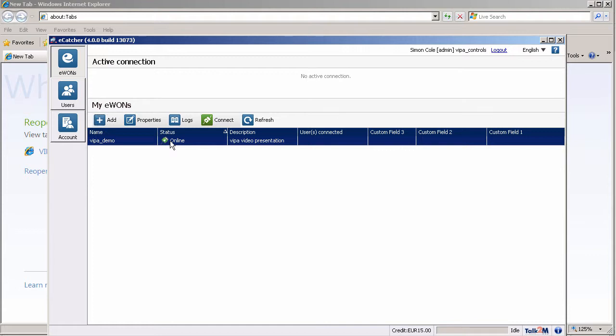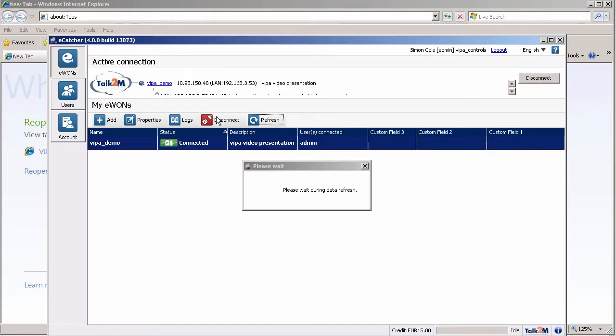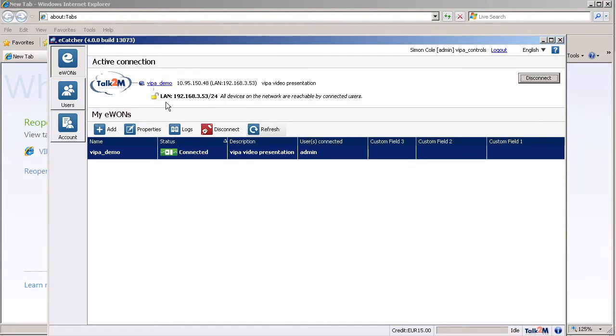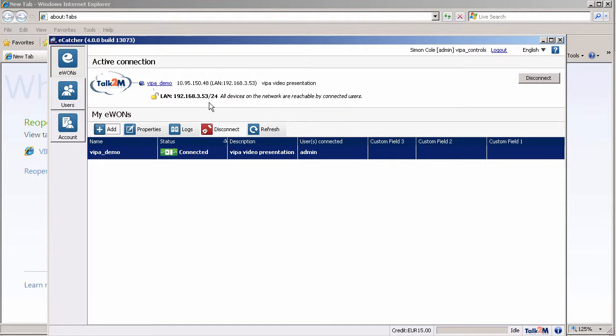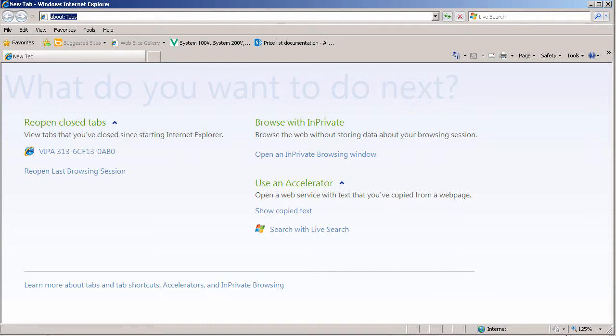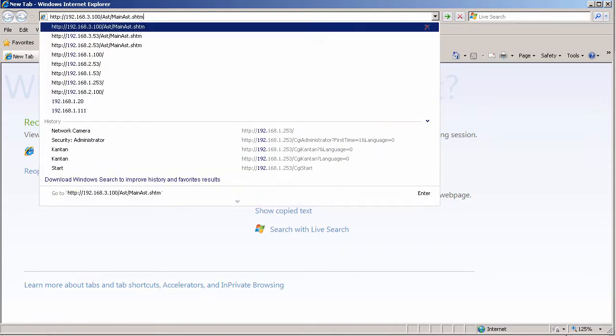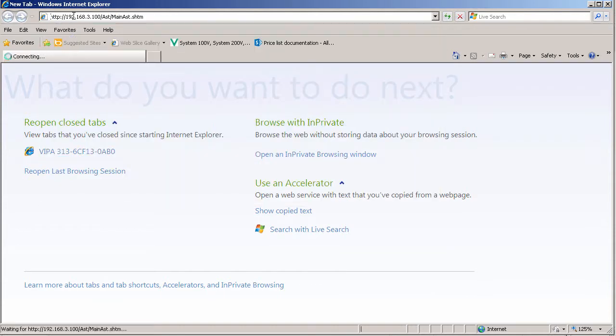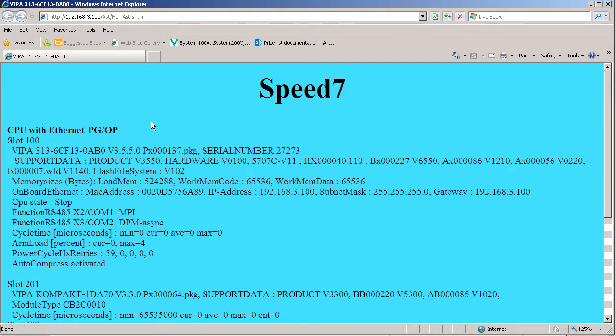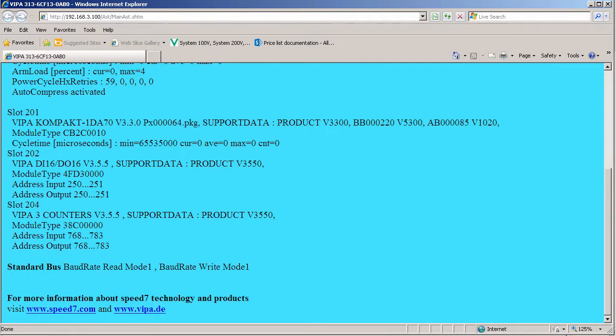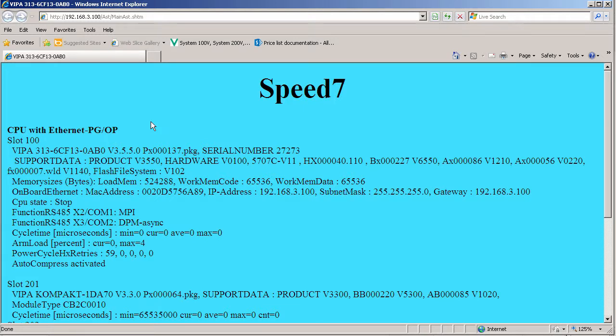So here we are now online with that particular device. Let's connect to it through the Talk2M server — and we have established a connection. This is the LAN address behind the device, so anything within this subnet you can now connect to directly. For example, right now I have a VIPA PLC at address 192.168.3.100, and we can now view the internal web page of that PLC.